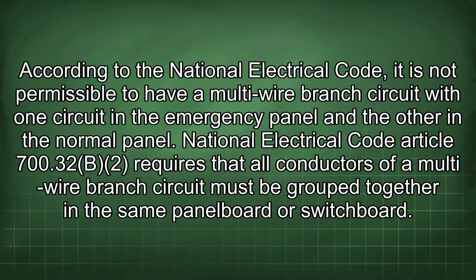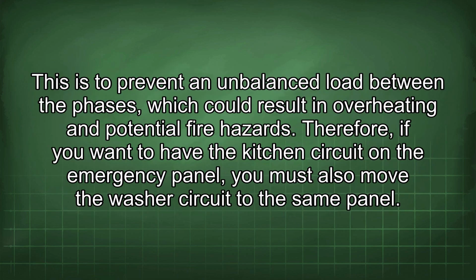According to the National Electrical Code, it is not permissible to have a multi-wire branch circuit with one circuit in the emergency panel and the other in the normal panel. National Electrical Code Article 700.32(B)(2) requires that all conductors of a multi-wire branch circuit must be grouped together in the same panel board or switchboard. This is to prevent an unbalanced load between the phases, which could result in overheating and potential fire hazards.